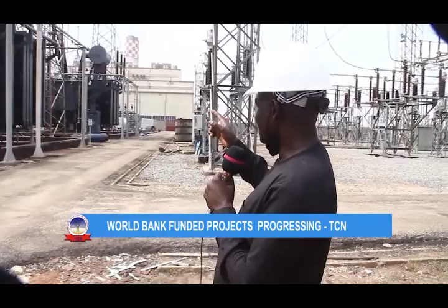There is also upgrading of power transformers at the substation, as the old transformers are overloaded. Look at these two transformers - this is a 2 by 150 MVA power transformer, 330/132 kV. These two are presently overloaded, and management is looking at upgrading the station with another transformer. At the back, this is a plinth to accommodate another power transformer, that is 300 MVA, 330 by 132 kV.